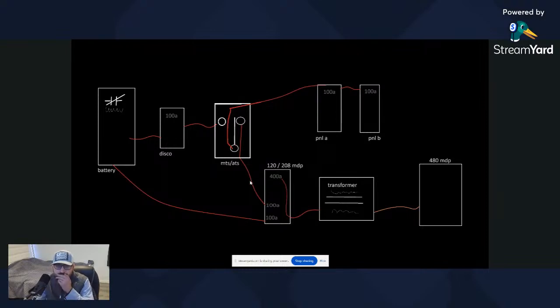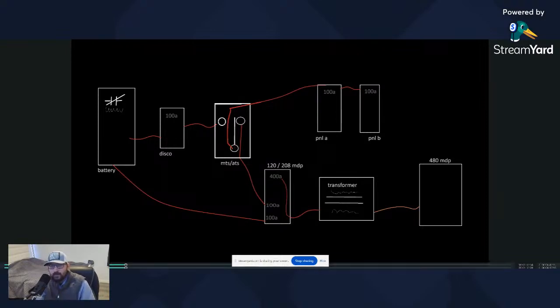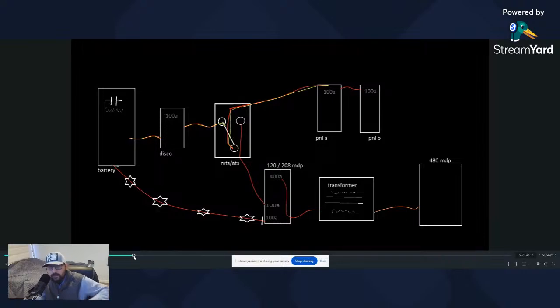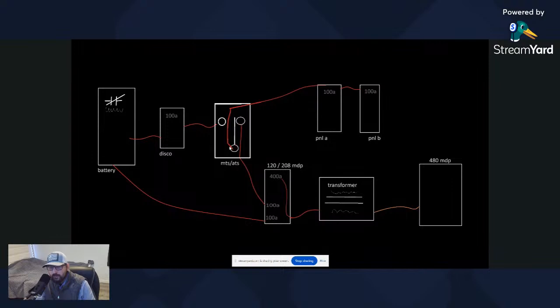Now, what we have here, this is a switch. And what happens with this switch is you're going to see, if you look at this white portion here, you're going to see where that switches over. You can see the white moving now right here on this ATS, which is an automatic transfer switch or a manual transfer switch. So what we're going to see here is this bottom pole right here is the common. And what's common about this is that this is always going to have power, whether it's going to be switched over here and going fed from this 100 amp breaker, or whether it gets switched over here and it's fed from this battery backup cabinet. So this is our common.